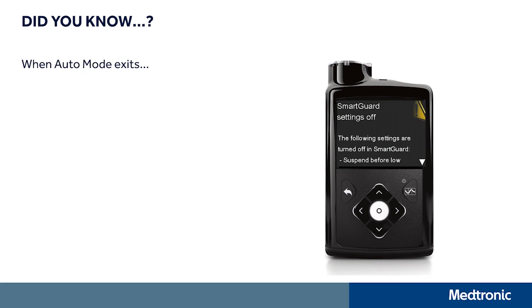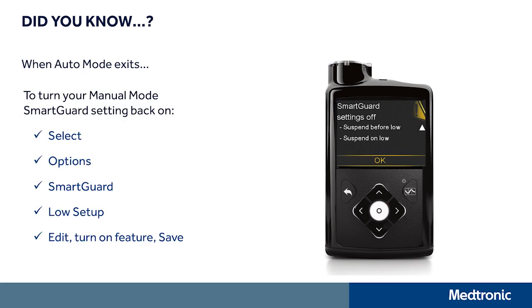Did you know when you exit out of auto mode, your manual mode SmartGuard settings like suspend before low are off? If you plan on staying in manual mode for a while, such as during steroid use, turn those settings back on. For example, you may have been using suspend before low before you started auto mode and you'd like to use it again in manual mode. To turn your suspend before low on, press select, go to options and press select on SmartGuard, go to low setup and press select. Then select the feature you want on and press next, done, and save.